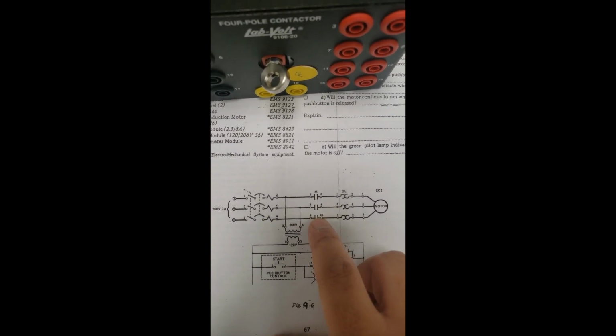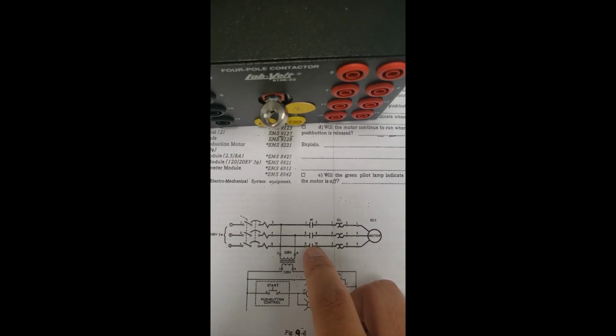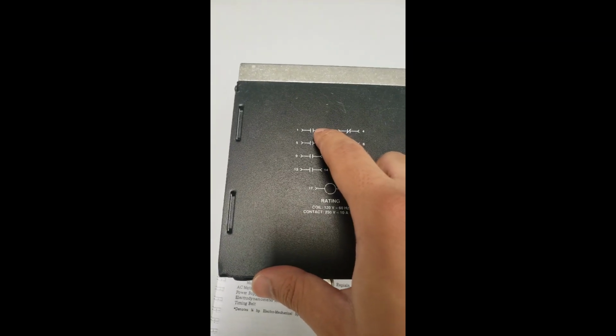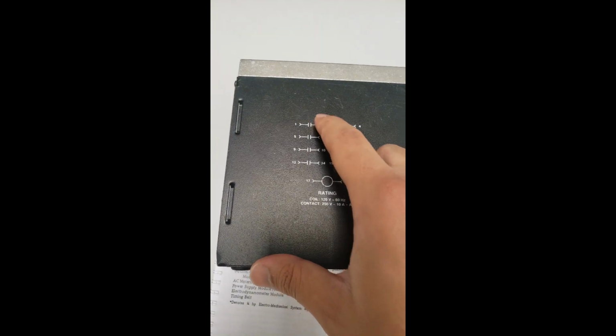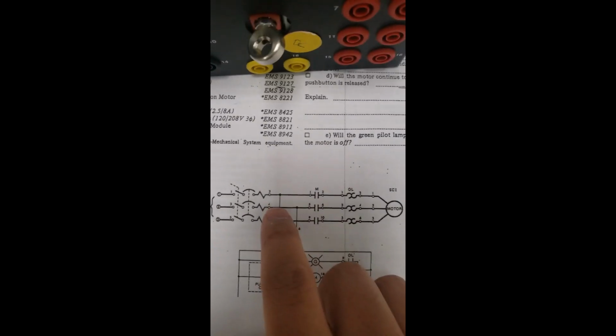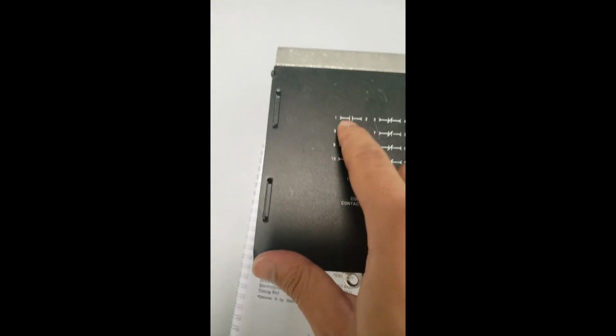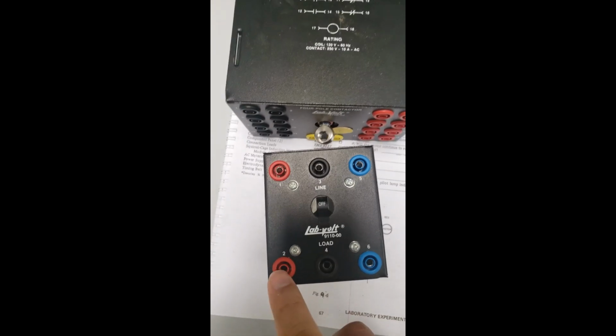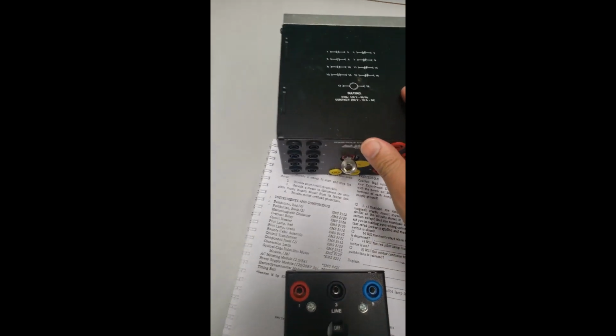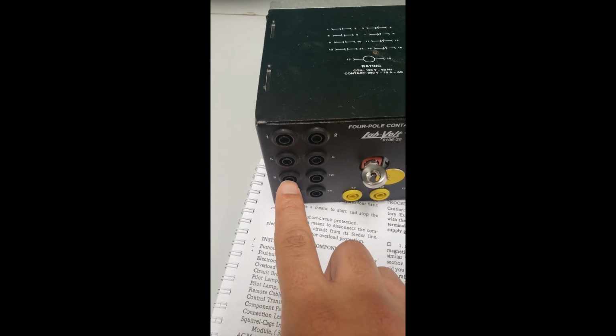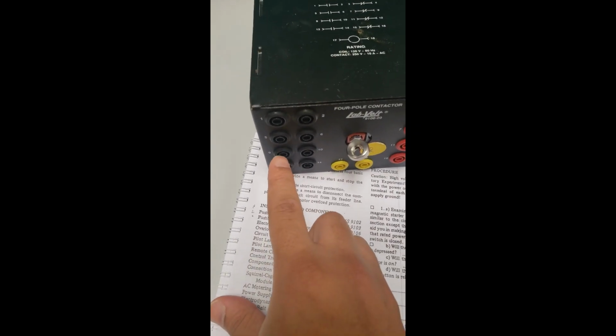I have to choose 3 normally open contacts of the contactor. It doesn't matter if I choose this one, this one, this one, or this one, this one, this one. I have to choose only 3. So, to make it easier, from 2 to 1, which is this one, then from 4 to 5, which is this one, and from 6 to 9.